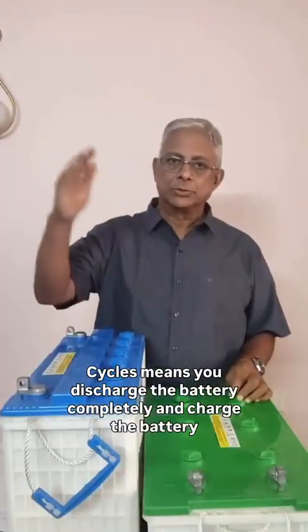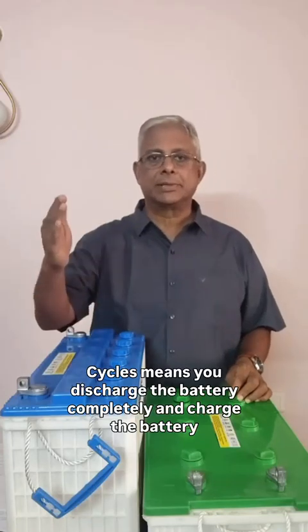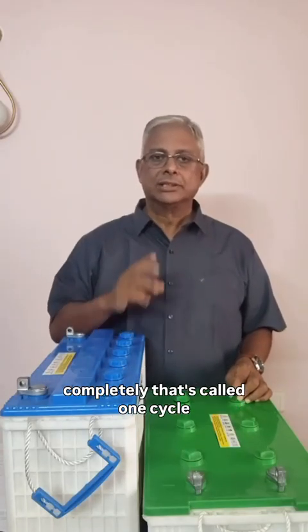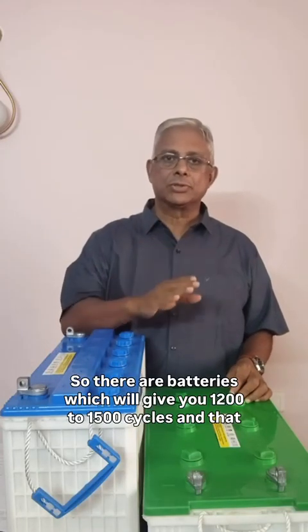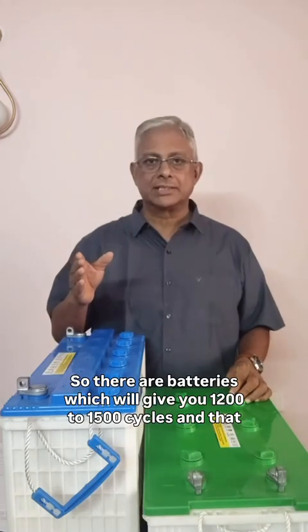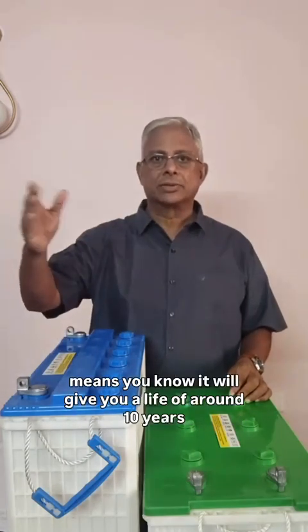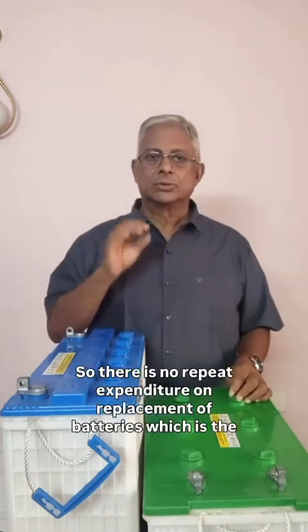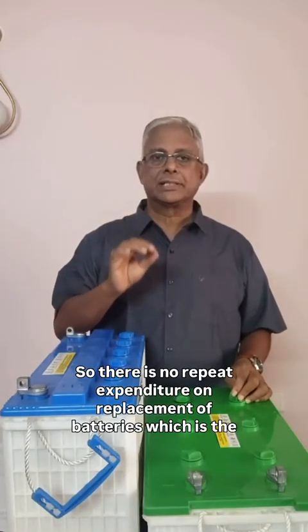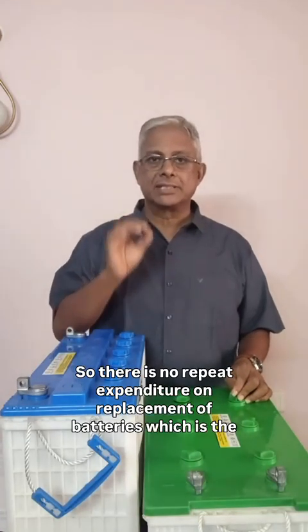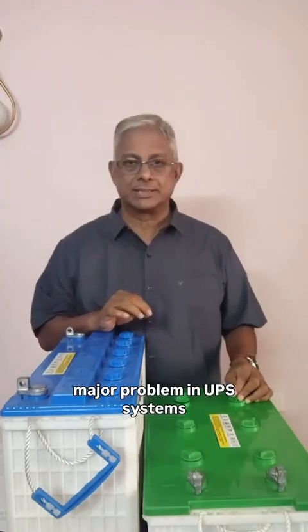A cycle means you discharge the battery completely and charge it completely - that's called one cycle. So batteries which give 1200 to 1500 cycles will give you a life of around 10 years, so there is no repeat expenditure on replacement of batteries, which is the major problem in UPS systems.